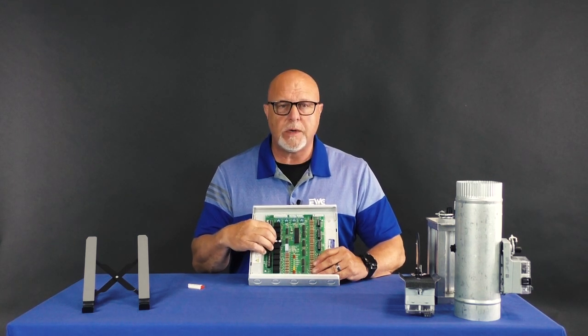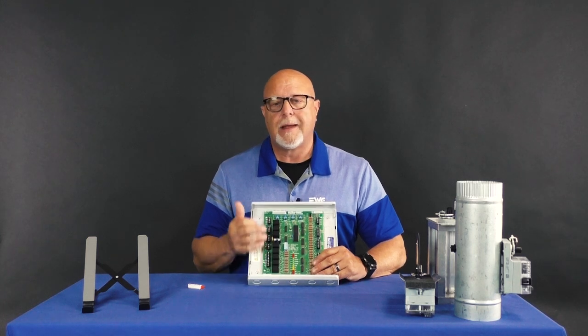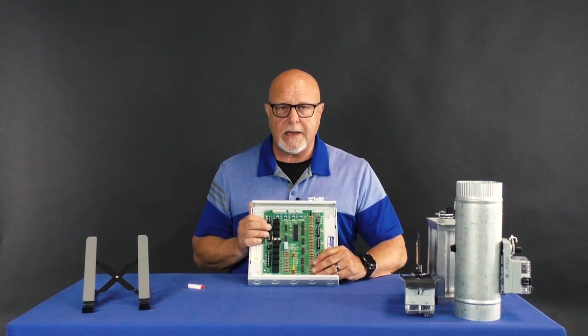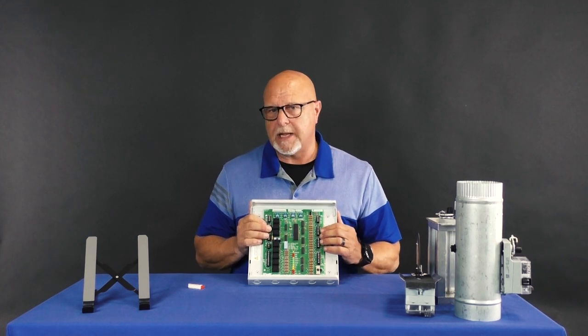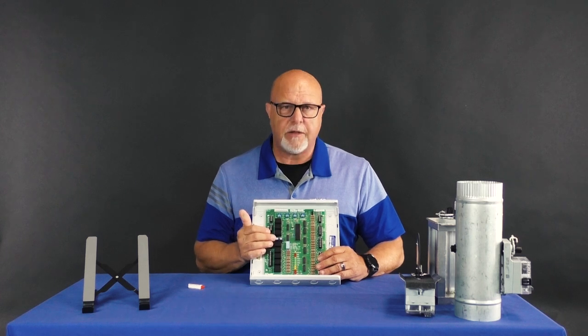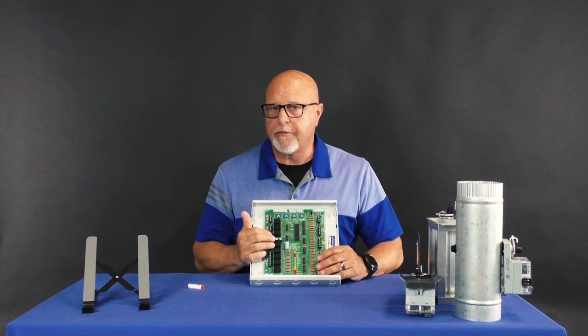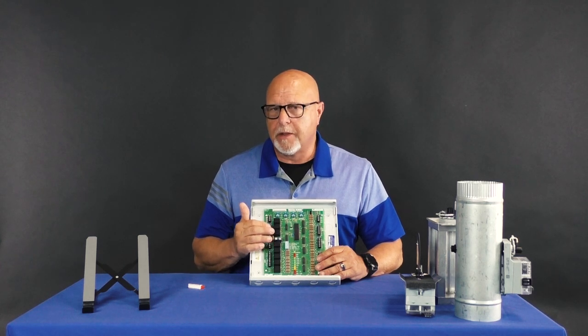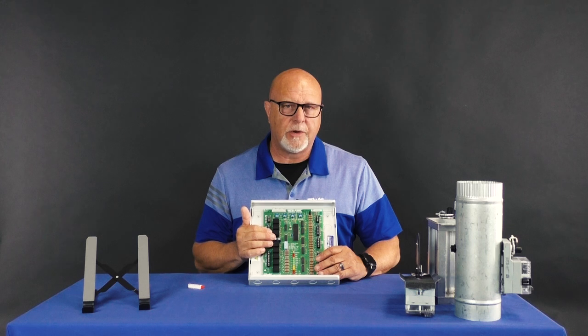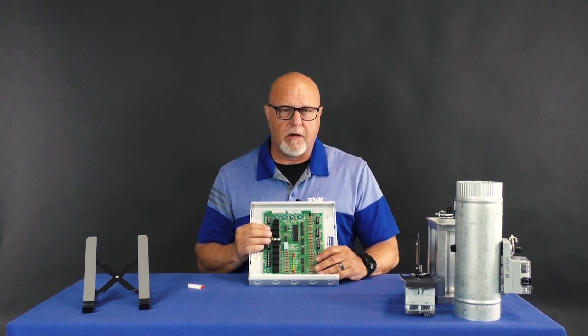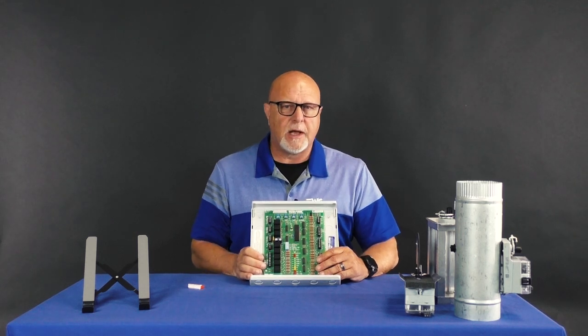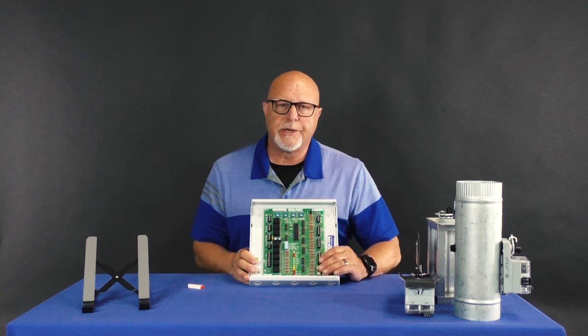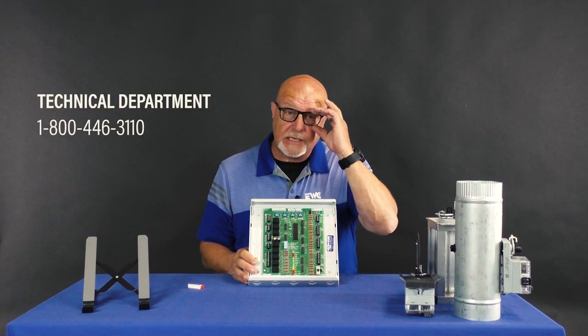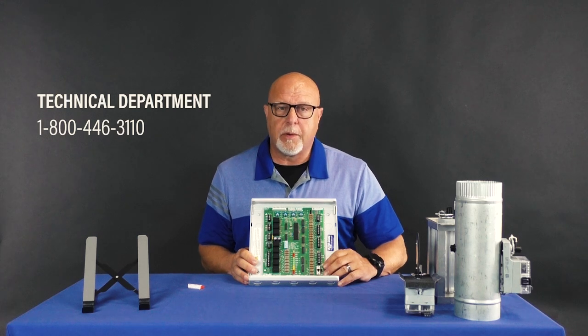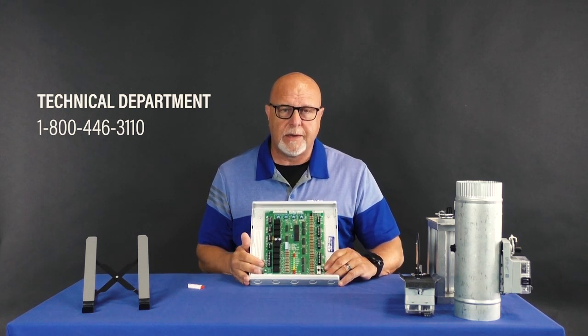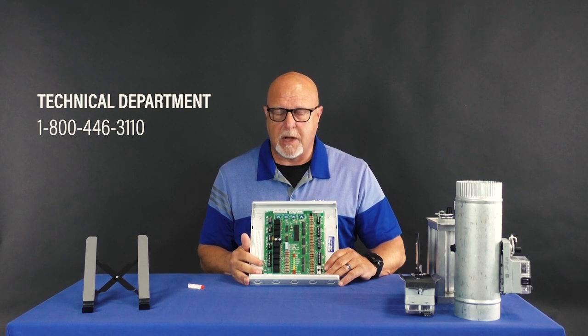You come up here and you feel it, oh, it's warm, that means you're off on thermal overload and you have a short, thereby indicating that you need to go and identify that short. And once that short is identified and corrected, this polyfuse will reset all by itself, therefore eliminating the need to replace a damaged board. Always check to make sure that this is not off on thermal overload. It's always best, if you get to the job site and there is a problem with the board, to call our engineering department at 1-800-446-3110 and ask for our technical department and have them assist you in diagnosing whether or not this board has been damaged.